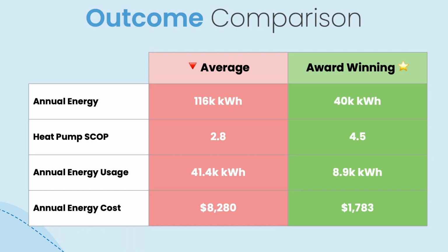I wanted to put this into some results. To summarize, the annual energy in terms of heat output for the average is 116,000 compared to the award-winning one, reduced massively to 40,000. Because the SCOP is pretty poor for the average one, annual energy usage is 41.4 thousand kilowatt hours, costing $8,280 for the year.